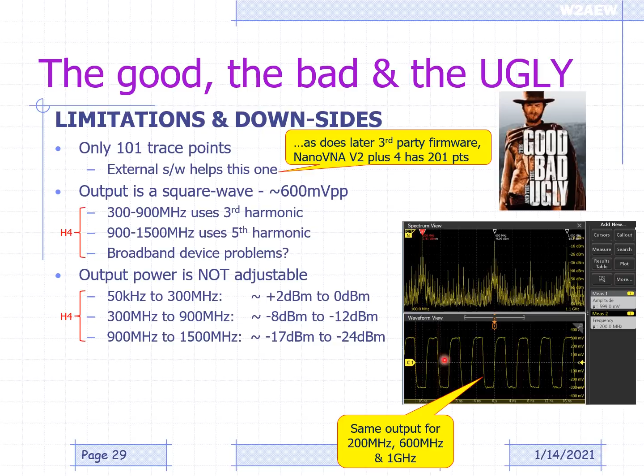And the output power, the output amplitude, is not adjustable. It's about a milliwatt, about 0 dBm at the fundamental. It's about 10 dB lower at the third harmonic, and another 10 to 12 dB lower at the fifth harmonic. So again, is that going to be correct for the device you're measuring? Because you can't really adjust it. It also means you can't do things like gain compression measurements on an amplifier. Also, the receive reference level is not adjustable. So if we are measuring an amplifier, I would probably have to pad down the output by the same amount that the amplifier brought it up, so that I would get about the same amplitude going into the VNA to make an accurate measurement.